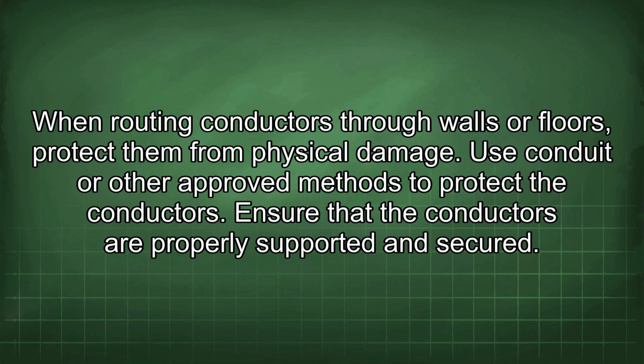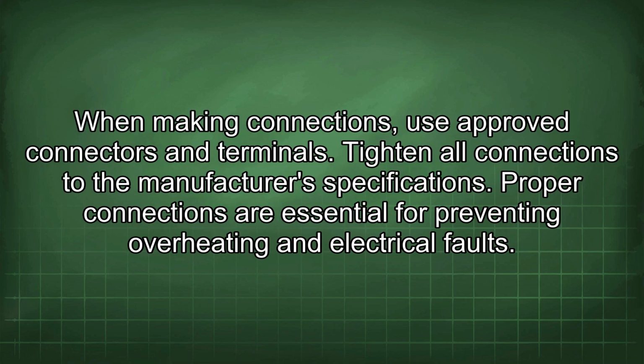Ensure that the conductors are properly supported and secured. When making connections, use approved connectors and terminals. Tighten all connections to the manufacturer's specifications. Proper connections are essential for preventing overheating and electrical faults.